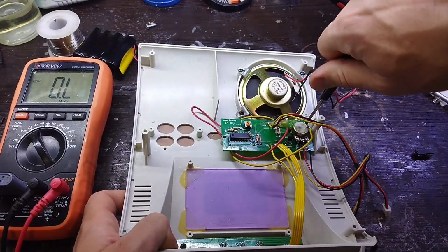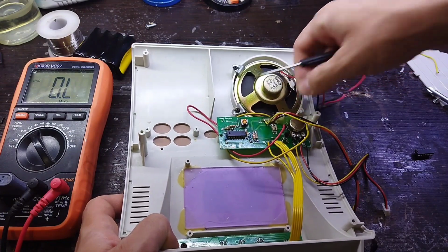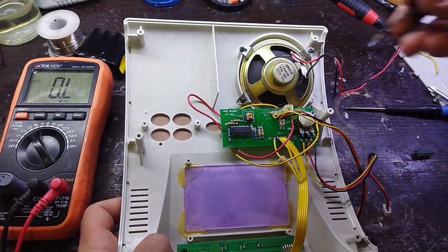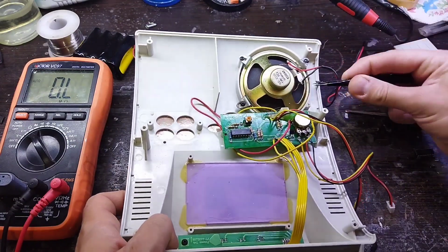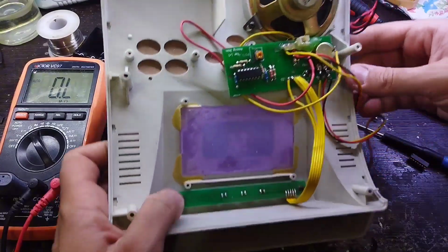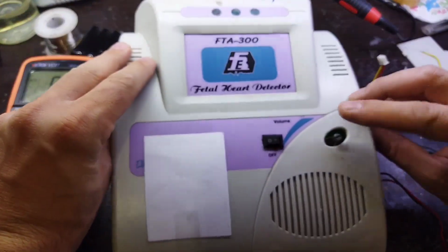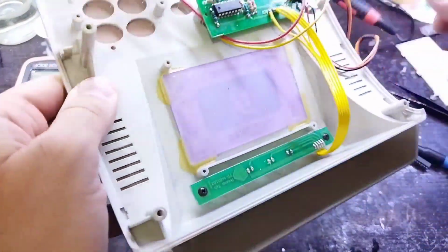This device is based on Doppler theory. It works by means of a piezoelectric transducer probe, which is related to an ultrasonic system. In fact, the SONOKID device reflects the sound of the fetus's heart, which can be heard through the speaker of the device.